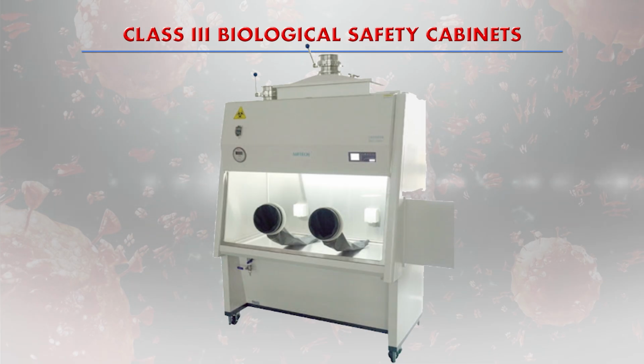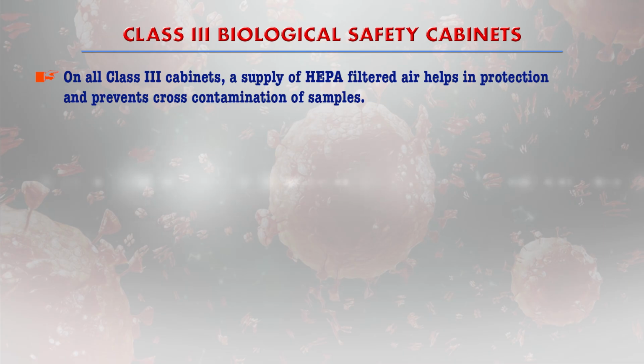tight. The only thing is there are two glove ports in front of the cabinet where you can put your hands inside and then conduct whatever experiment you want to do. Negative pressure relative to the ambient environment is maintained within the cabinet. On all the class 3 cabinets, a supply of HEPA filtered air helps in protection and also helps in preventing the cross contamination of the samples.